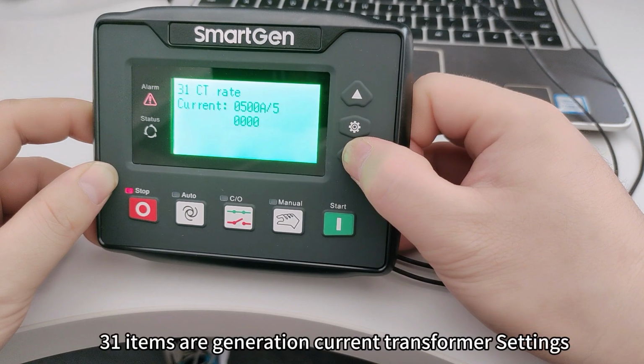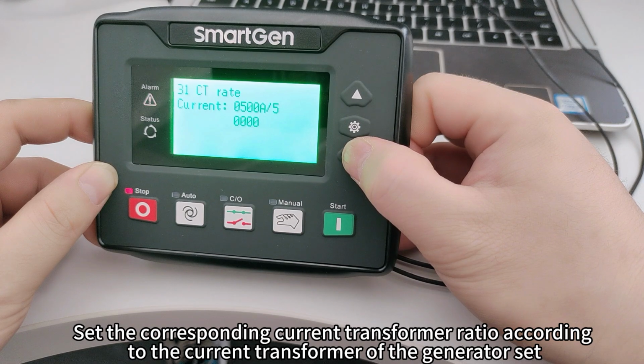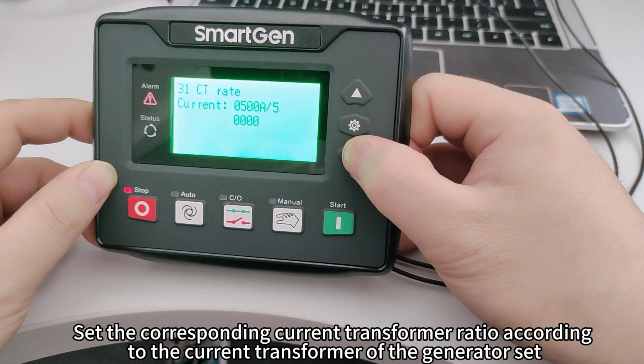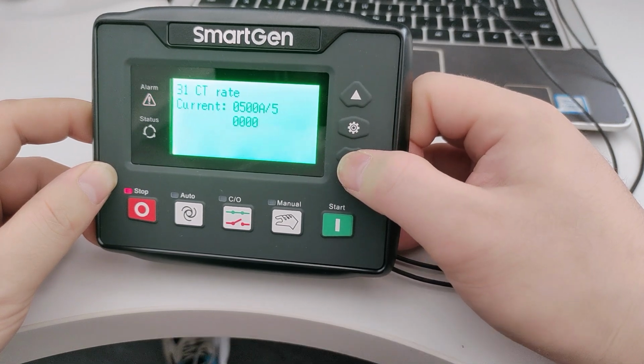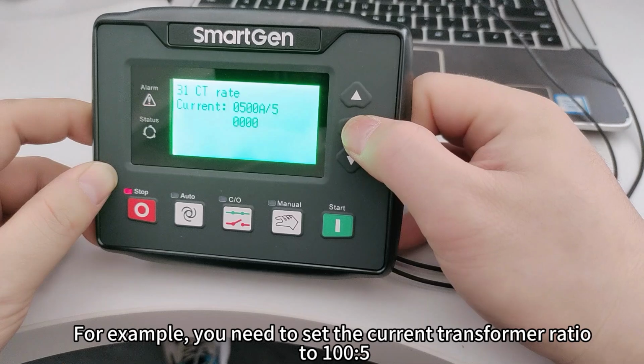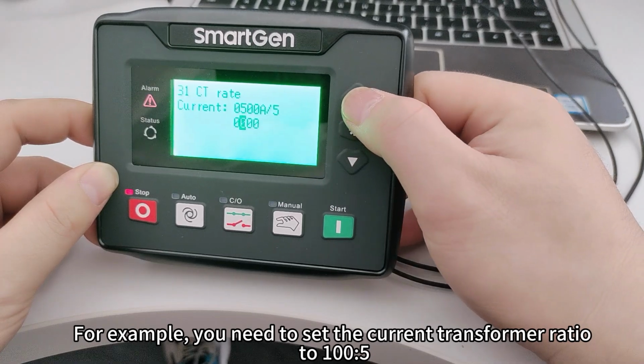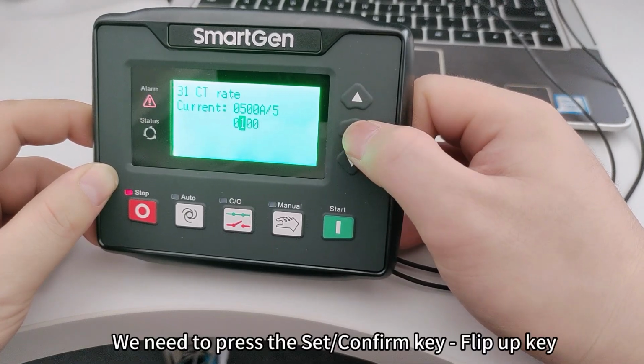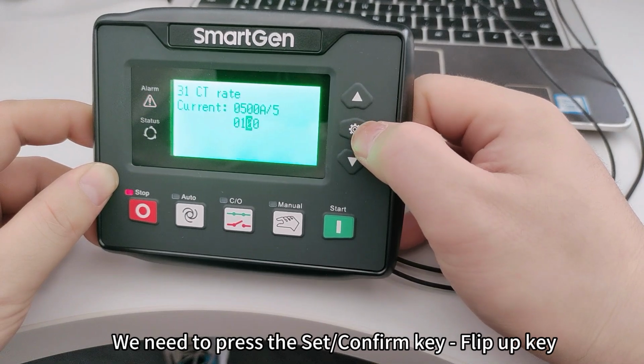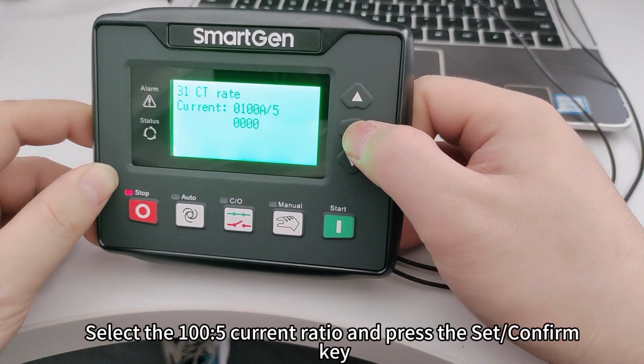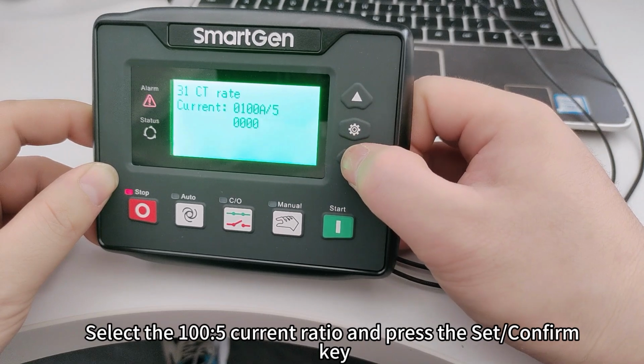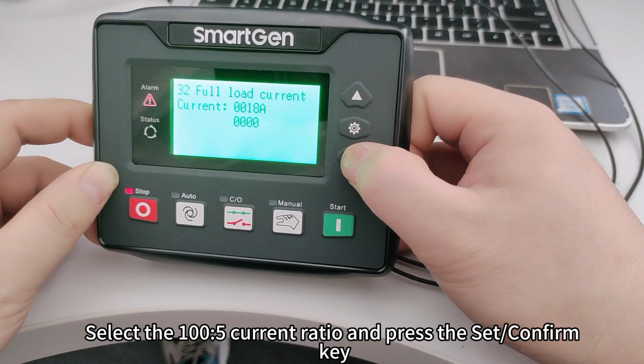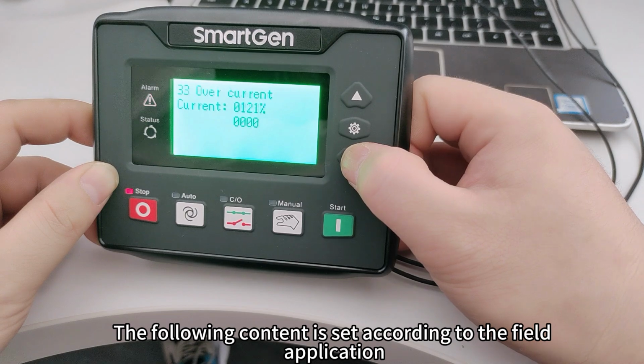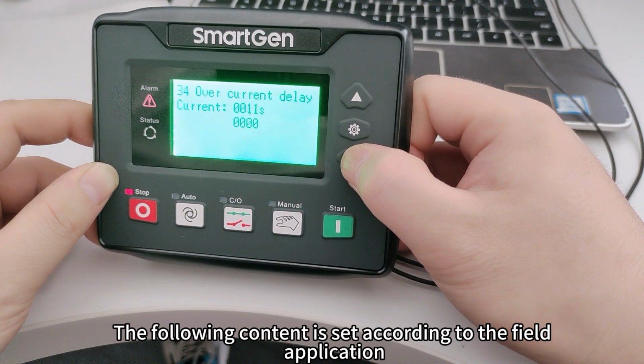Item 31 is the generator current transformer setting. Set the corresponding current transformer ratio according to the current transformer of the generator set. For example, if you need to set the current transformer ratio to 100:5, we need to press the Set Confirm key, the flip up key, select the 100:5 current ratio and press the Set Confirm key. The following content is set according to the field application.